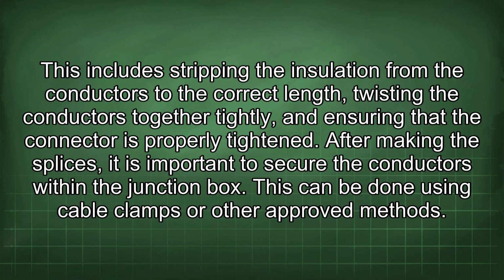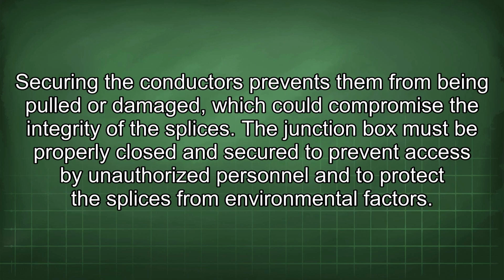After making the splices, it is important to secure the conductors within the junction box. This can be done using cable clamps or other approved methods. Securing the conductors prevents them from being pulled or damaged, which could compromise the integrity of the splices.